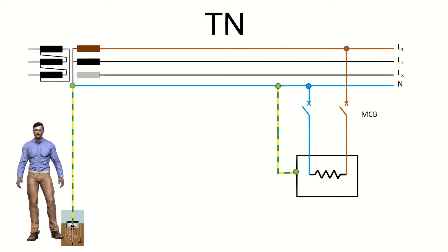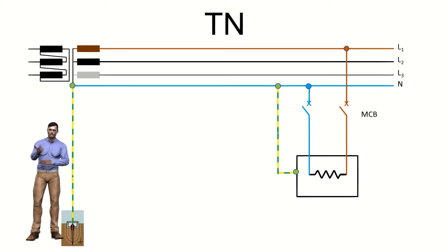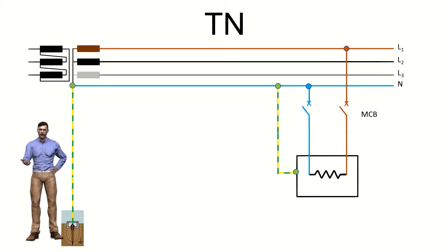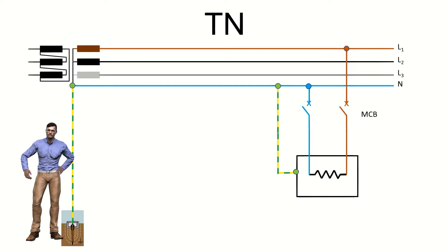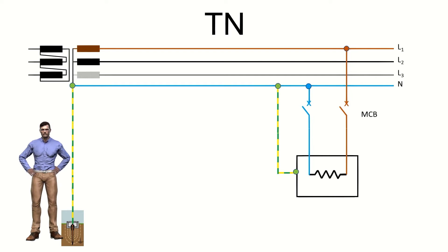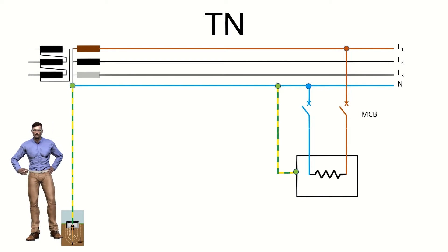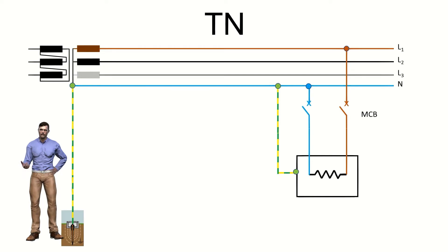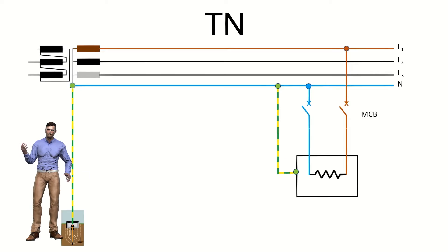In this way we can combine these letters to obtain the following schemes. In a TN system, the neutral of the supply is connected to earth directly, while the masses of the receiving loads are connected to the same earth connection of the neutral. The TN electrical diagrams can be divided into three types depending on whether the neutral and the protective conductor are separated or not.